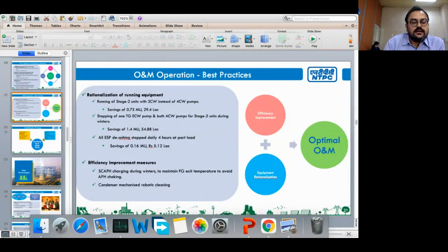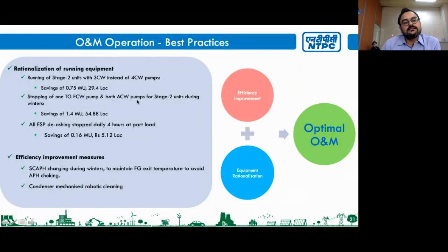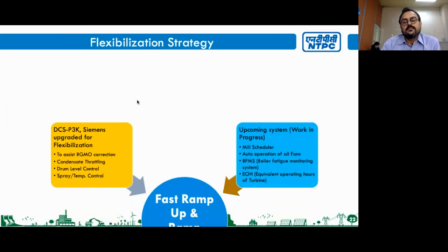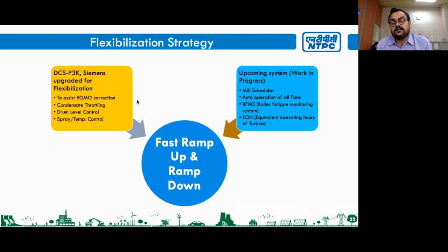And the last point that I'd like to talk about is, for efficiency improvement, we have done condenser mechanized robot cleaning and SCAPH charging during winters. Now, this is our flexibilization strategy for faster ramp up and ramp down. In our stage 2 units, we have installed the P3K Siemens system, and we have upgraded it for flexibilization. This assists us in RGMO correction, condensate throttling, drum level control, and spray and temperature control.